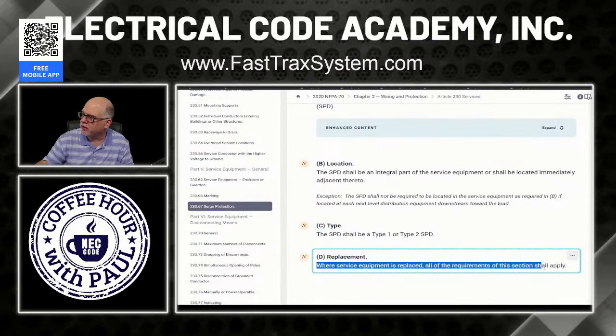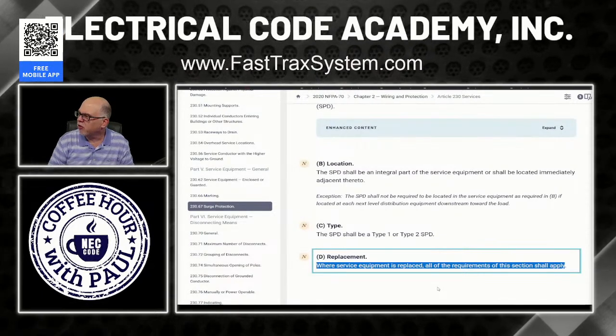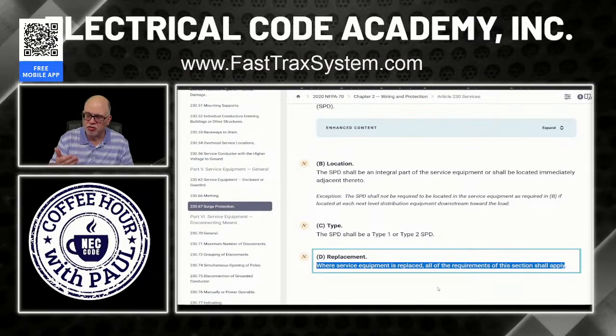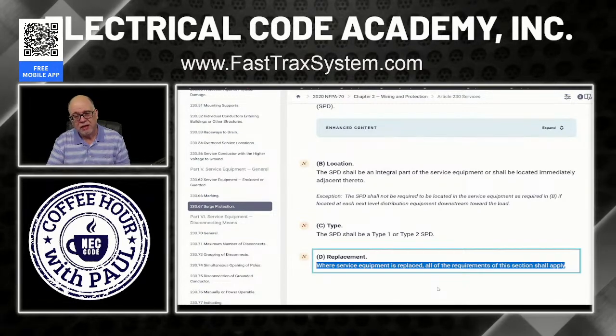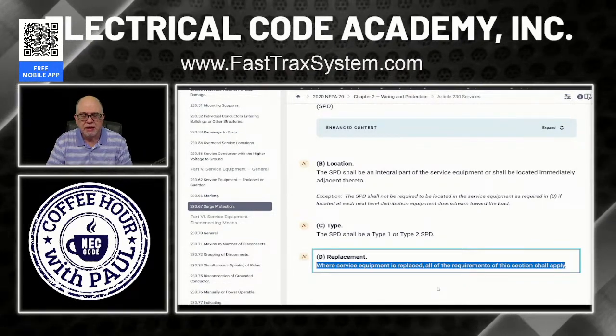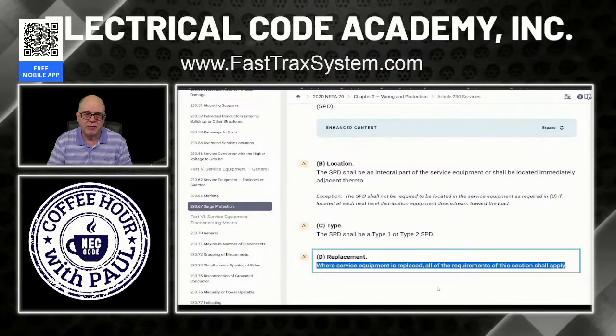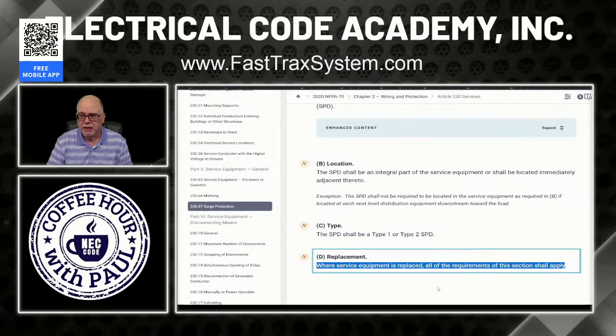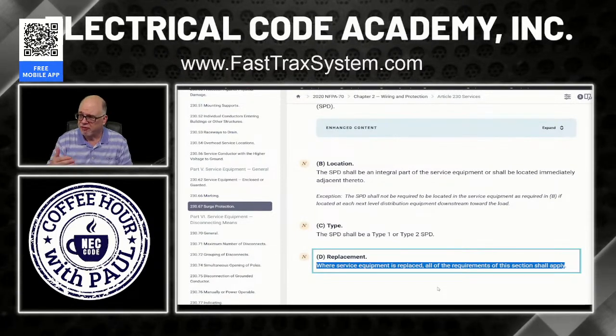This is the important one here to remember: where service equipment is replaced, all the requirements of this section shall apply. So if somebody is doing a service replacement and it wasn't there at the old service, it wasn't required at the time, obviously, because this is a 2020 code. But when you put that service back, guess what? They're now going to have to put in these surge protective devices. So if you have a big multifamily complex and they change the service or do some changes there, then it's going to affect the SPDs.